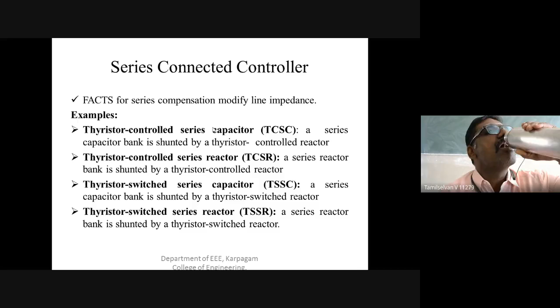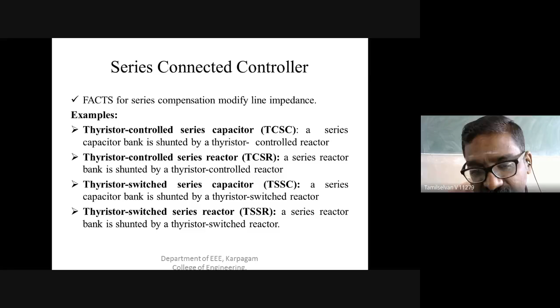FACTS devices here offer a thyristor controlled series capacitor, often called TCSC. It means the series capacitor will be shunted by a thyristor controlled reactor, or thyristor controlled series reactor, called TCSR. It's a series reactor shunted by a thyristor controlled reactor. Or TSSC, meaning thyristor switched series capacitor. The series capacitor bank will be shunted by a thyristor switch reactor, or TSSR, thyristor switch series reactor.